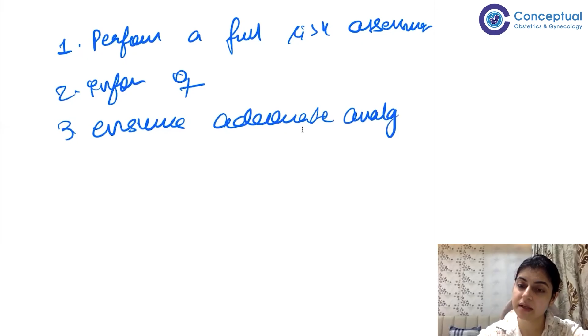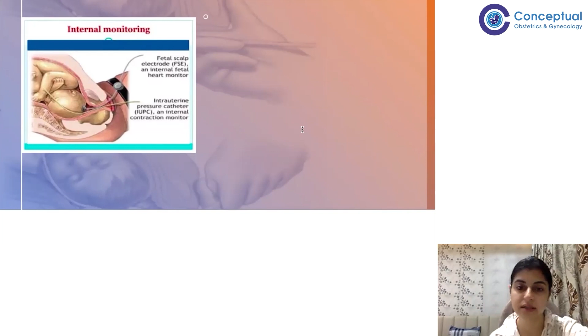Now, there is something called internal monitoring, which is done through fetal scalp electrodes or internal fetal heart rate monitors. Intrauterine pressure catheters are available which measure internal contractions. Internal monitoring uses a catheter connected to a strain gauge pressure sensor. The pressure of the fluid system is measured and converted into electrical signals. This measures the intensity and also the duration of contractions more accurately. So if anybody asks you in the exam, CTG measures well but is not very sensitive. What is more sensitive is intrauterine pressure catheters, which transmit the fluid pressure signals into electrical signals, so that it measures more adequately.